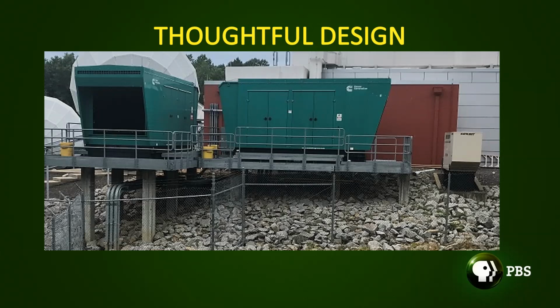Talking about thoughtful design, there are a couple of things I wanted to call your attention to. You'll notice there are 2 identical emergency generators. We have 2 complete separate power systems, either one of which can carry our full load. These are megawatt generators, tapped back to 750 kilowatts. Our normal load to carry our entire technical center is about 300 kilowatts max, that's with the tower lights on and everything, more than one uplink HPA powered up. So that's a pretty reliable number.